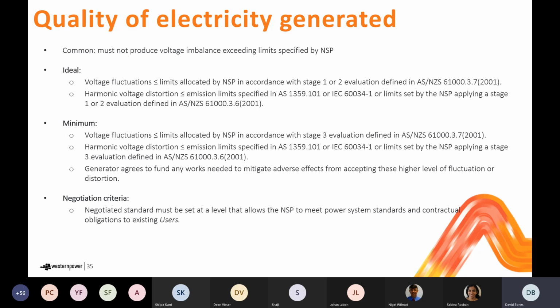And the condition is that if a generator is operating at that minimum or more relaxed level, they've agreed to fund any future mitigation works that might be needed as a result of operating at that higher distortion level. Or some of those mitigation works might actually be to invest to tighten the level of distortion they create at a time in the future when it is actually causing a problem for other network users.